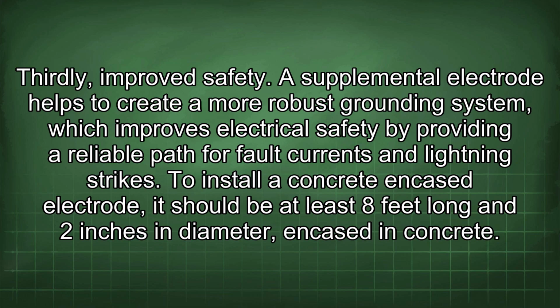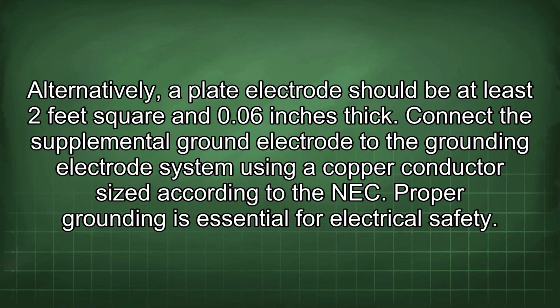To install a concrete encased electrode, it should be at least 8 feet long and 2 inches in diameter, encased in concrete. Alternatively, a plate electrode should be at least 2 feet square and 0.06 inches thick. Connect the supplemental ground electrode to the grounding electrode system using a copper conductor sized according to the NEC.